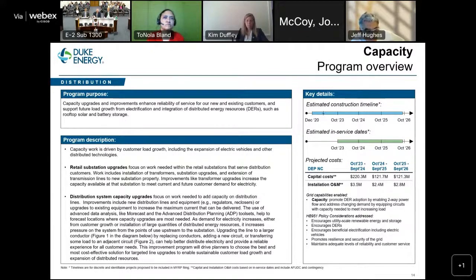There's also the automated distribution planning tool set, part of ISOP, which includes automated solutioning. This allows a planner to analyze not only individual thermal overloads at the circuit level, but also adjacent circuits and substations in that area, leveraging Morecast peak data to determine how best to alleviate that thermal overload. That may include balancing load transfers, permanent load transfers to other circuits, conductor and device upgrades — more traditional capacity implementation — as well as non-traditional solutions.